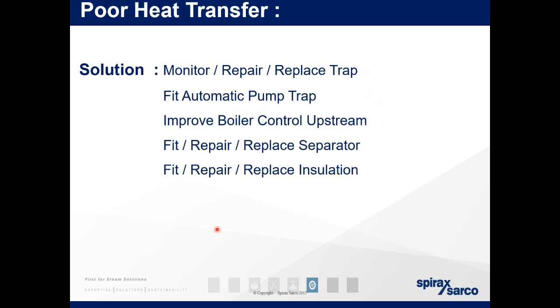So the solution: we can monitor, repair and replace the steam traps, fit automatic pump traps to remove the stall, improve boiler control upstream. So that's talking again about the on-off control versus modulating. Fit, repair and replace separators, and fit, repair, replace insulation. Again, I haven't touched on the separators and insulation because we've covered that earlier. But again, all these will help produce a more efficient energy system.